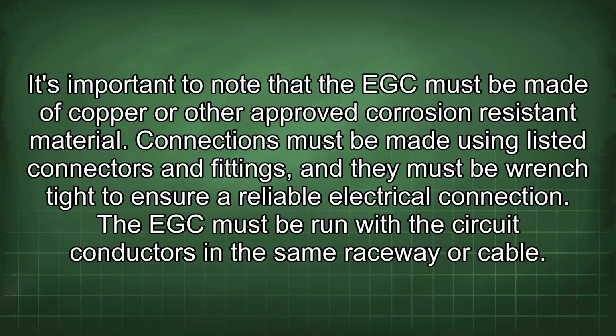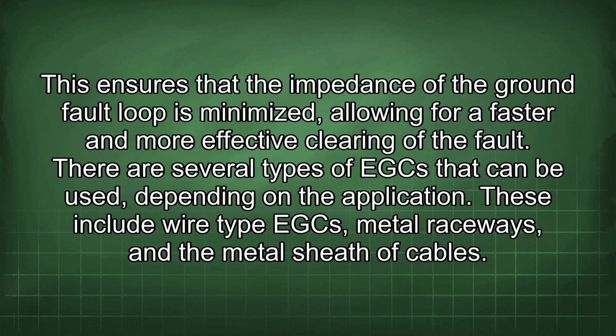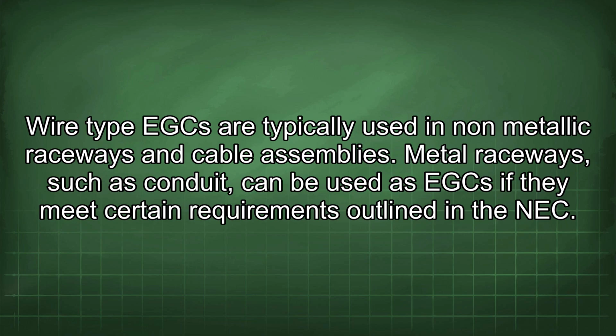Connections must be made using listed connectors and fittings, and they must be wrenched tight to ensure a reliable electrical connection. The EGC must be run with the circuit conductors in the same raceway or cable. This ensures that the impedance of the ground fault loop is minimized, allowing for a faster and more effective clearing of the fault. There are several types of EGC that can be used depending on the application. These include wire-type EGC, metal raceways, and the metal sheath of cables. Wire-type EGCs are typically used in non-metallic raceways and cable assemblies. Metal raceways, such as conduit, can be used as EGC if they meet certain requirements outlined in the NEC.